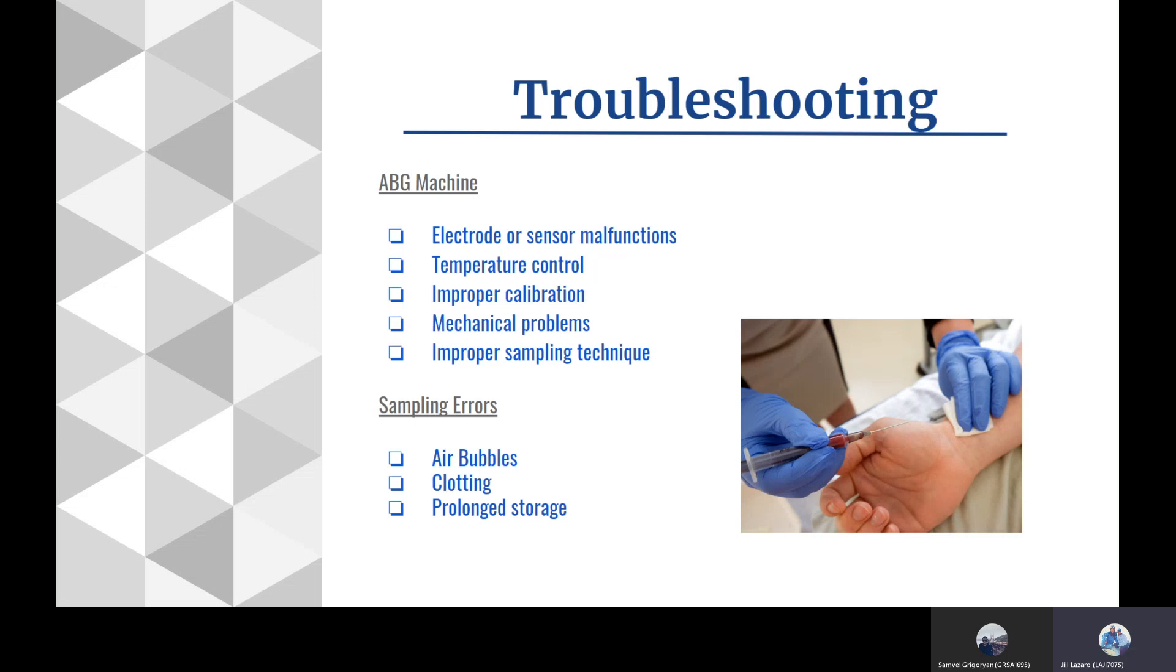As far as sampling, there are a couple of things we need to look at. We need to make sure we don't have any air bubbles in our samples. We need to make sure our blood is not clotted and that we're not keeping our samples for a long time. After 15 minutes, we need to take another sample. These are common things to look at for troubleshooting in regards to our ABGs, analysis, and calibration.